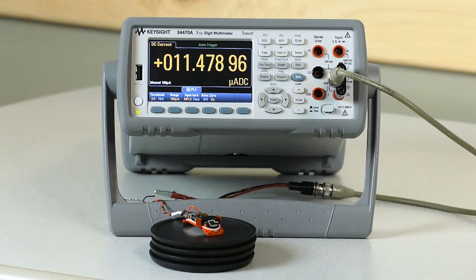Notice the resolution we have going way down. The 34470 can measure very high resolution in these quiet slow modes, down to 1 microamp full scale in fact.